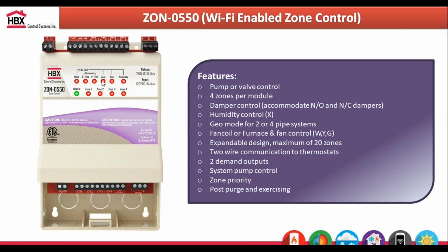So getting back to the zone controller, again, it's an all-in-one HVAC zone controller. We can do 4 zones per module, and it is expandable up to 20 different zone controllers per system. Through the zone controller, there are a lot of different features. Again, you can do zone pumps, zone valves, dampers. We get zone priority if you are using it for just in-floor heating. There's post-purge and exercising every 72 hours for those pumps. There are 2 demand outputs to send a signal to your boiler or heat pumps or for your domestic hot water tank. We also have geothermal modes built in, so you can put it into a geothermal mode where we can do 2 or 4 pipe systems.